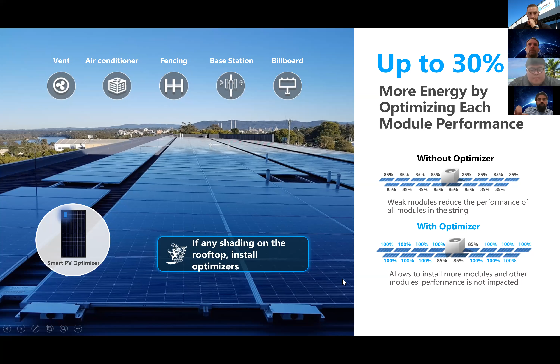Multi-MPPT gives higher yields. So a single MPPT inverter with multiple strings, one string shaded, or on a different tilt, or a different azimuth, will reduce the output of the whole MPPT. Whereas in our solution, which is now proudly copied by others too, one string shaded only reduces power on that MPPT.